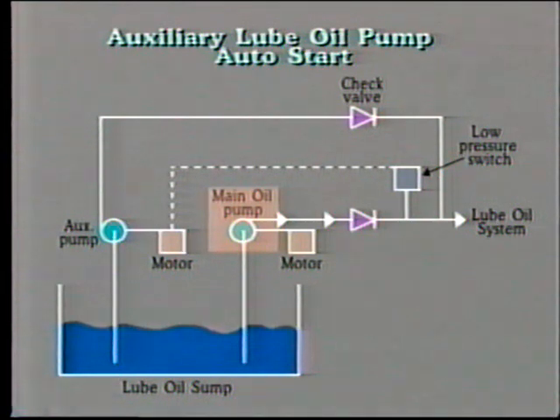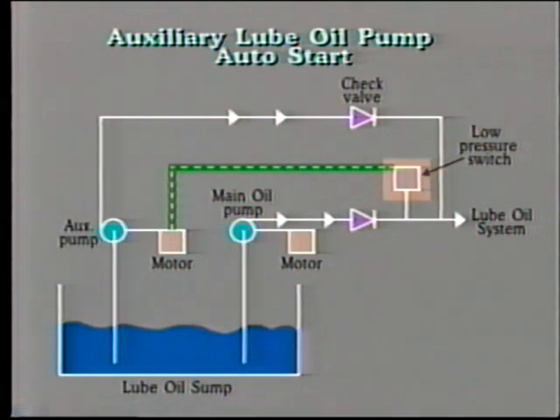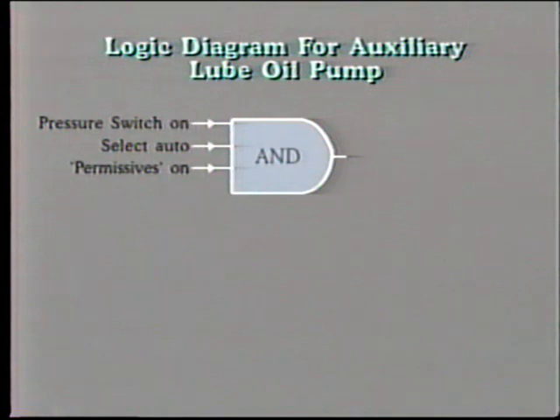Here we are looking at the main oil pump, which is providing lube oil for a gas turbine. An auxiliary oil pump is installed so as to maintain lube oil flow in case of failure of the main oil pump. The auxiliary oil pump will cut in automatically when this low pressure switch detects that the oil pressure has fallen to its set point. This logic diagram shows that in order to energize the auxiliary oil pump starting relay, we need to fulfill several conditions. The pressure switch must be on due to low oil pressure. The auto manual switch must be set to auto, and all permissive circuits for the pump must be on.